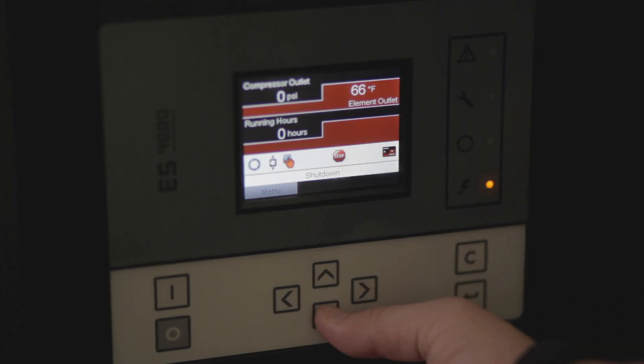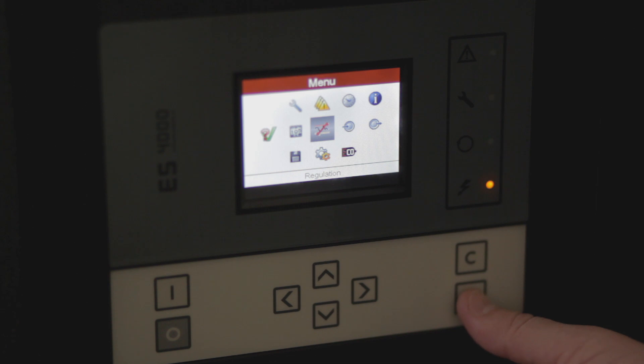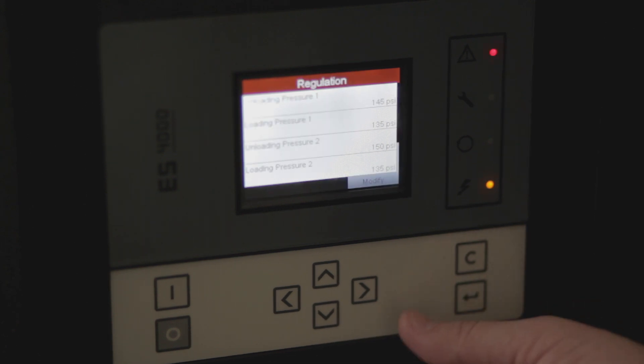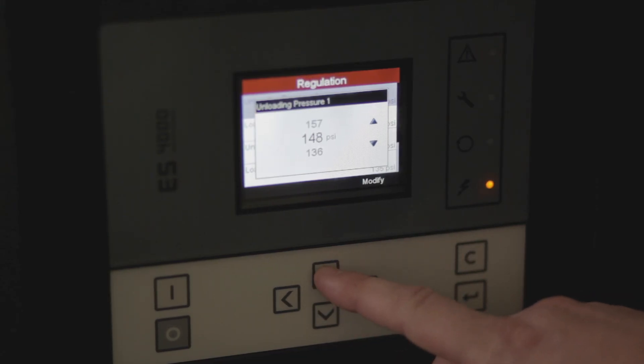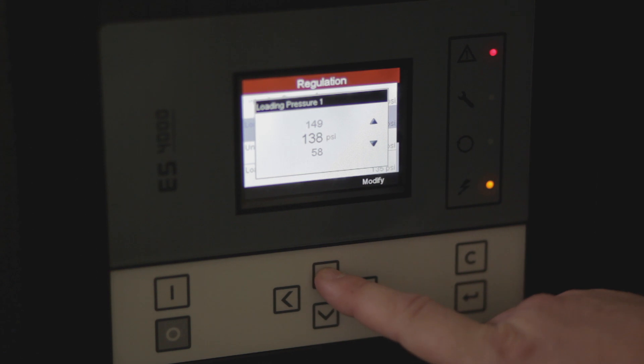The first thing we're going to look at doing is adjusting the pressure on your compressor. You're going to need to enter the main menu. We're going to scroll over to the regulation setting, modify our unloading pressure, and then modify our loading pressure. Now back out to the main menu and we're ready to go.